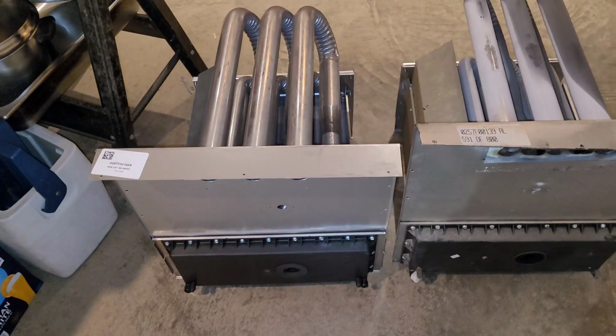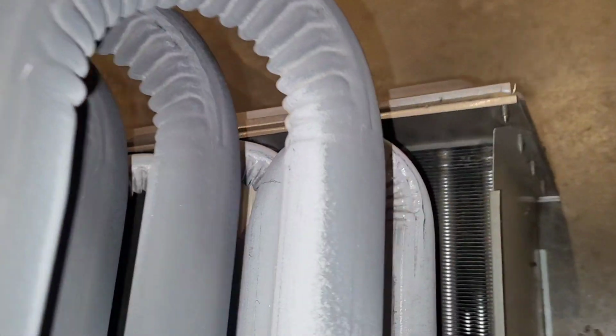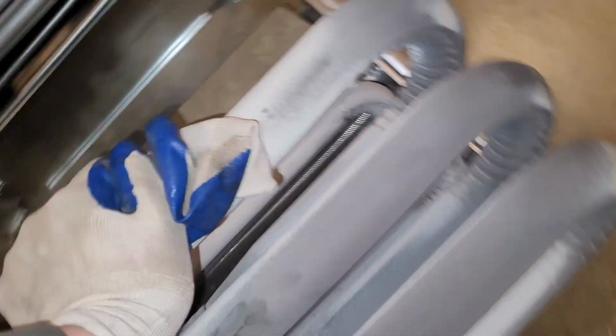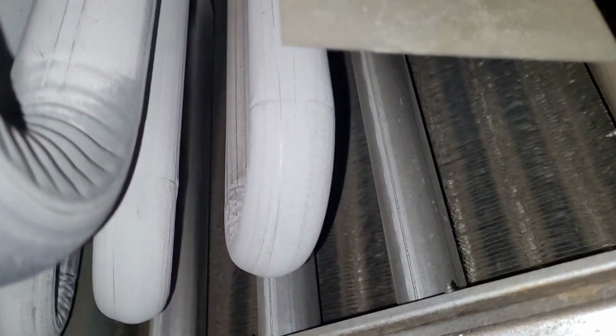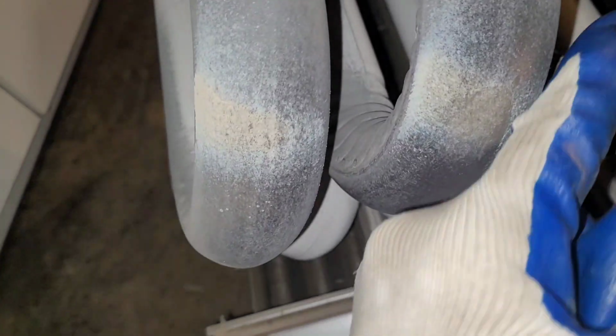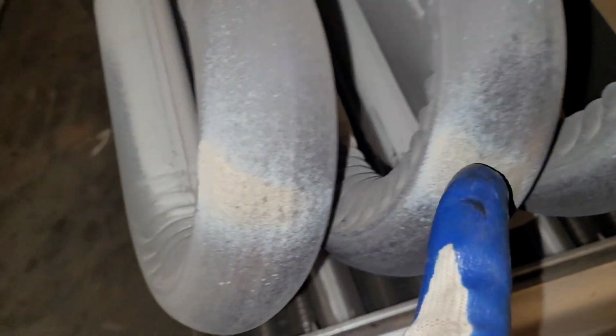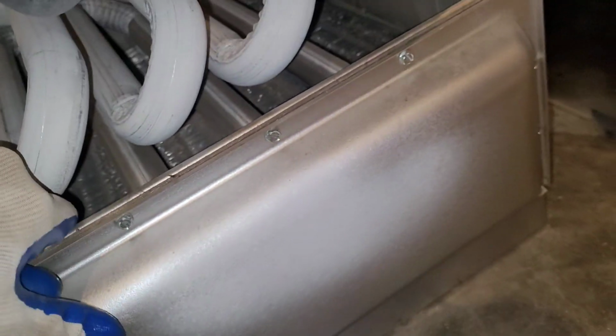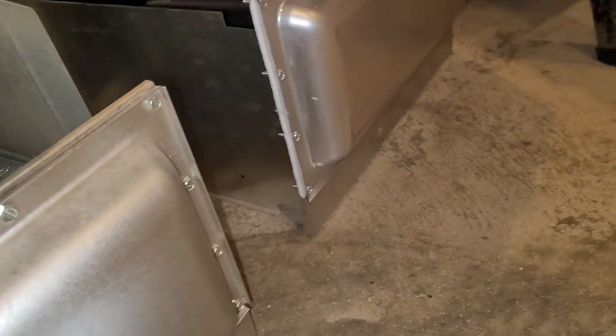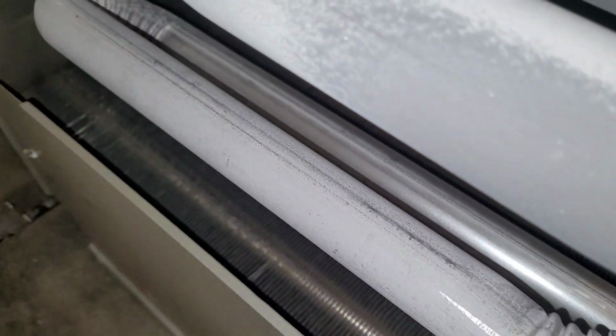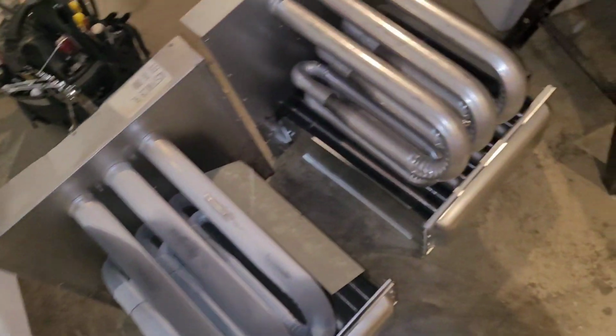Coil looks good. Blower looks good. The new and the old heat exchangers look pretty much identical. Don't think I see any actual holes through this one, so that's nice. Sometimes you'll get holes right on the edges of this loop right here. At least it's the most common that I see it. And looks like they got away with it. I don't think this is stainless steel. Yeah, not too bad. New one, just shiny but the same.